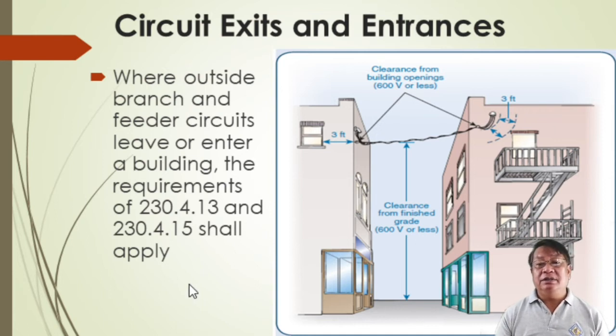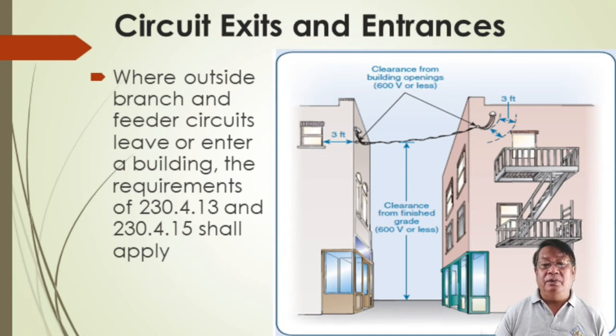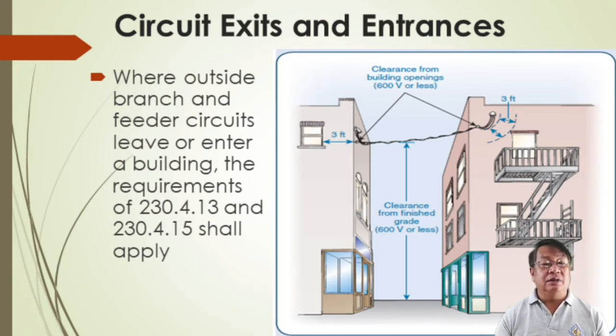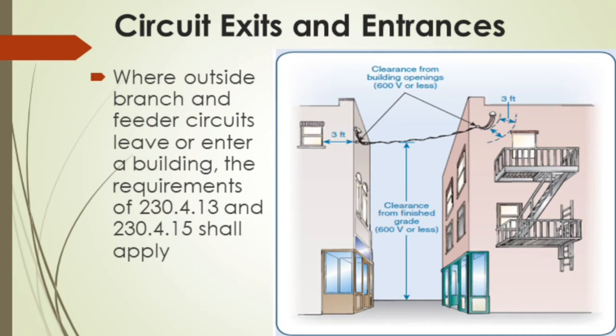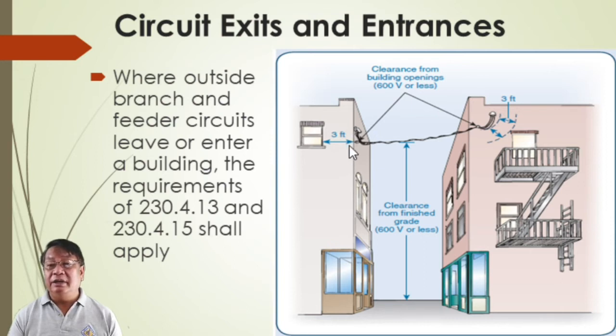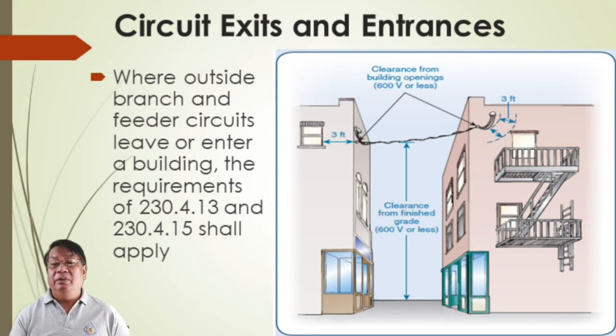For circuit exits and entrances where outside branch and feeder circuits leave or enter a building, the requirements at 230.4.13 and 230.4.15 apply. The service entrance should not be within three feet of a window or building opening — not three feet below or above, nor within that clearance.